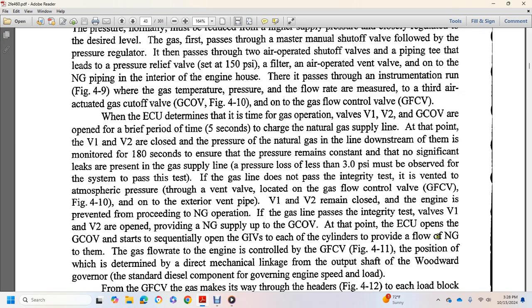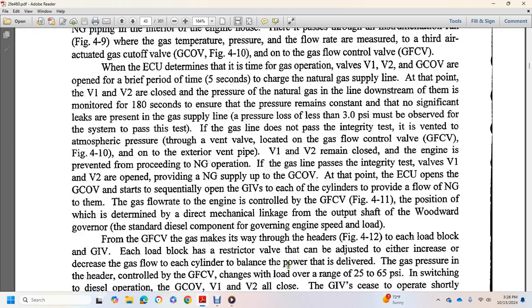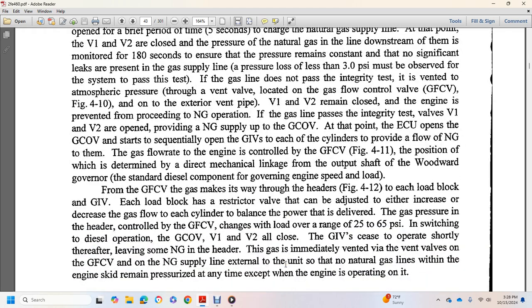Each cylinder is provided with a flow of natural gas. The gas flow rate to the engine is controlled with the gas flow control valve, the position of which is determined by a mechanical linkage to the output shaft of the Woodward governor, which senses engine speed and load. From the gas flow control valve, the gas goes through the headers to each gas inlet valve.